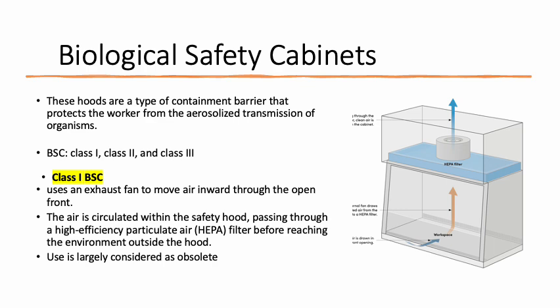Okay? So the basis of protection of biosafety cabinets is that they provide a controlled airflow within the safety cabinet that shields you from the aerosolization of potentially infectious organisms. This is done by providing a curtain of air, which is usually controlled via a system of a blower inside the biosafety cabinet. Okay? Now, in terms of classes, the class 1 biosafety cabinet uses an exhaust fan to move air inward through the open front.